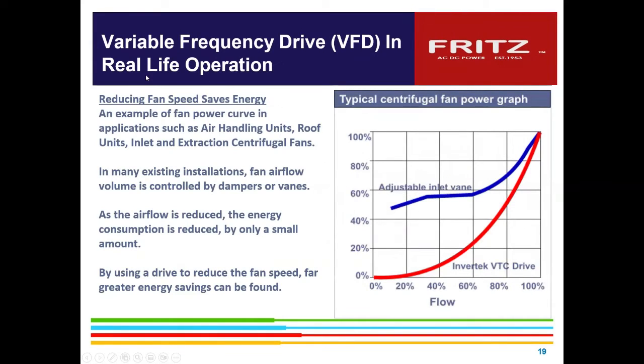So what we're talking about is what they call variable torque applications, like air handlers and pumps, where you actually get the cube law. A lot of people leave the motor at one existing speed, and then they just damper it with a vane. When you do it by just dampering, the power only drops down to about 60%. But if you did it with a variable speed drive and slowed that fan down to the same amount of flow, the horsepower drops so tremendously, because with dampering the motor continues to operate and continues to use a lot of power. So centrifugal fans, pumps, blowers, those types of things are definitely very good applications.